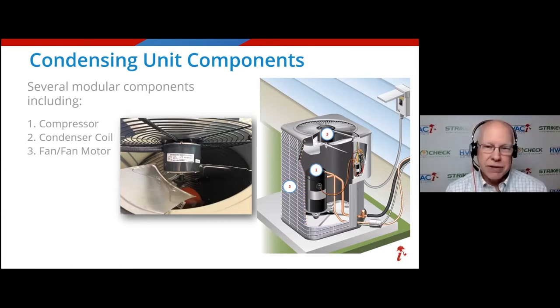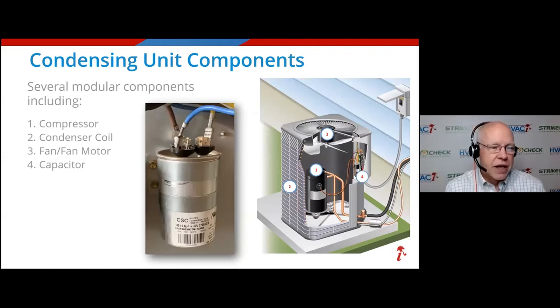When that happens, the refrigerant changes back to a liquid. It's given up its heat, so it's actually a cool liquid. So we've had a complete transformation from hot gas refrigerant to cool liquid refrigerant by the time it leaves this condensing unit. How's that? Hopefully there are some good questions coming on that, and we'll get to them at the end if you need more clarification on what's going on there. We're going to get away from the refrigerant circuit for just a minute.